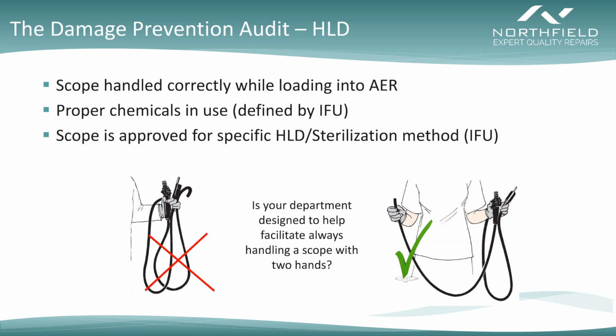We also want to make sure we've got the proper chemicals in use. This will, again, be defined for you by your IFUs. This is not something we get to make up as we go. We need to make sure that our scope is approved for whatever specific high-level disinfection or sterilization method that we are using. If you deviate from that, not only are you getting an unproven result from the high-level disinfection or sterilization process, but you're also very likely to see much more rapid damage being done to the device.